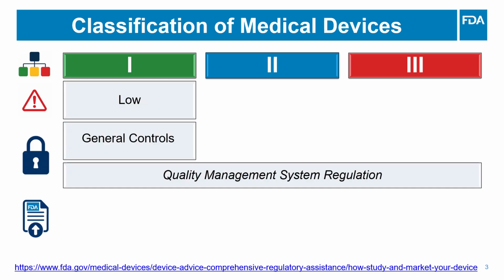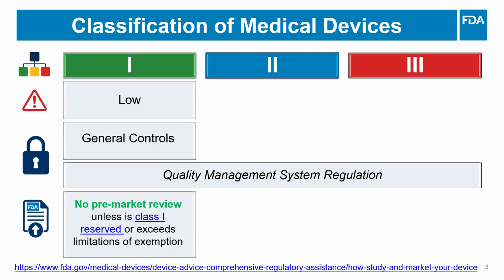Most Class 1 devices are exempt from the pre-market notification procedures, unless it's considered a Class 1 reserved device or exceeds the limitations of the exemptions, like new indications for use or technology that is different from what is described in the regulation. To be clear, manufacturers of Class 1 devices are required to validate them based on their intended use. While they don't need to submit any file to FDA, they must keep records internally, as this documentation can be examined by the agency during site inspections.